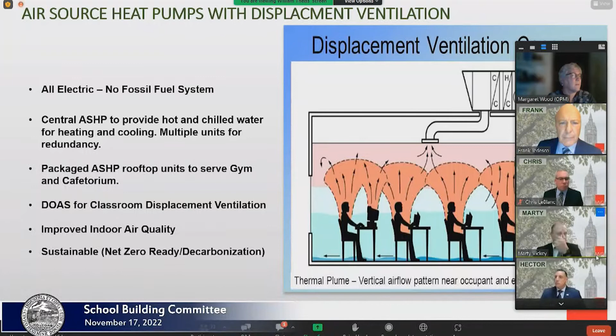Some benefits of this displacement system are listed here on the screen. For a typical classroom, there are no air handling units, fans, or drain pans located above the ceilings, which is a major savings on the maintenance side. Displacement ventilation systems provide very good indoor air quality, as dehumidified, non-recirculated fresh air is supplied at floor level through diffusers, washing over the occupants and then exhausted out through the ceiling, providing very high levels of indoor air quality.